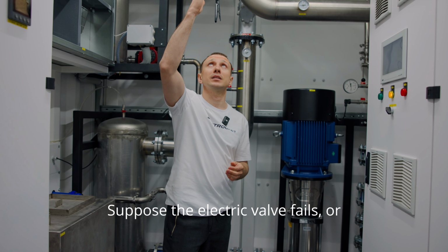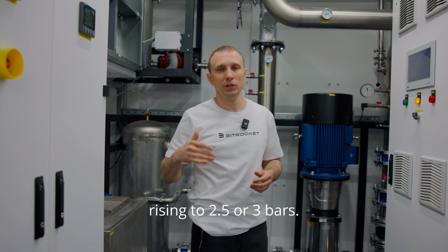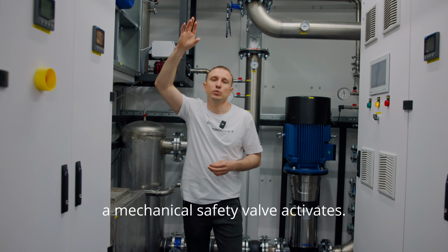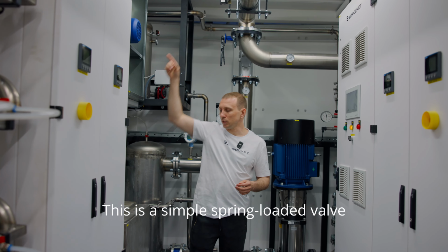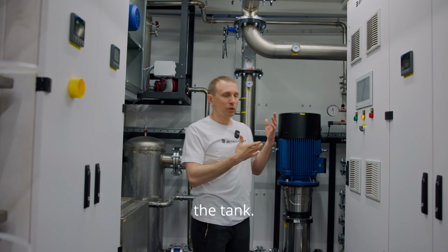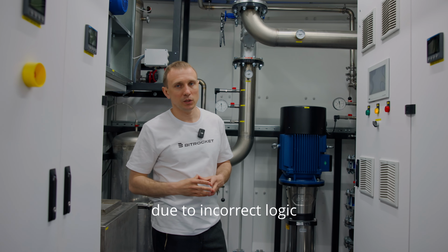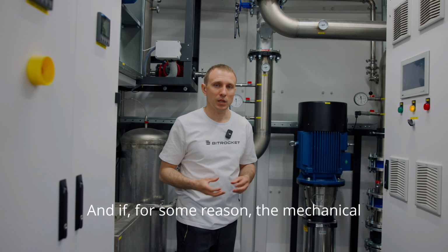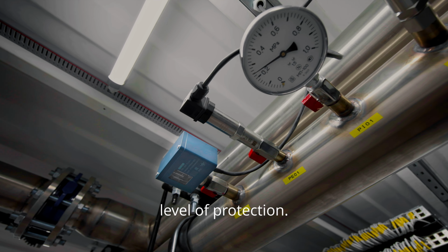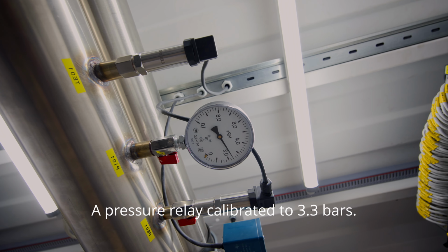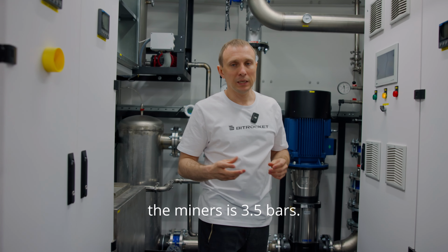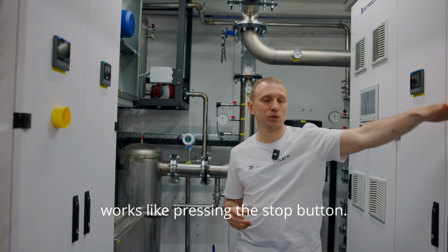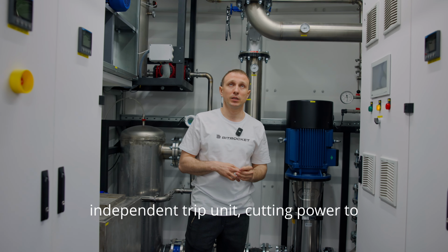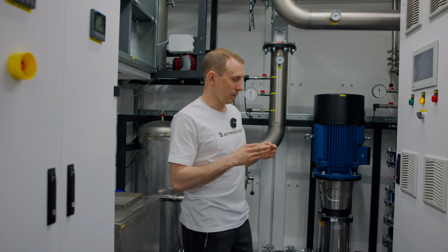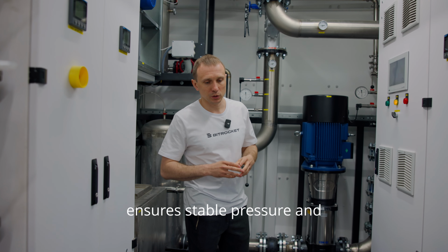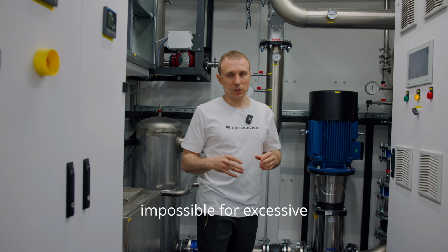Suppose the electric valve fails, or someone accidentally closes the shutoff valve before it, and pressure starts rising to 2.5 or 3 bars. At exactly 3 bars, a mechanical safety valve activates. This is a simple spring-loaded valve with no electronics, and its pipe also goes to the tank. So even if the electronic control fails due to incorrect logic or valve malfunction, the mechanical valve takes over. And if for some reason the mechanical valve fails to open, we have a third level of protection. A pressure relay calibrated to 3.3 bars. Maximum pressure for the miners is 3.5 bars. At 3.3 bars, the relay triggers, which works like pressing the stop button. A signal is sent directly to the independent trip unit, cutting power to the entire container. So this three-tiered protection system ensures stable pressure and makes sure that it's virtually impossible for excessive pressure to reach the miners.